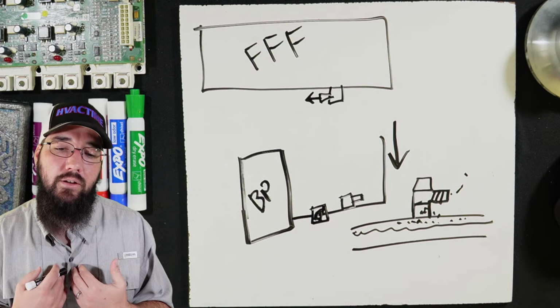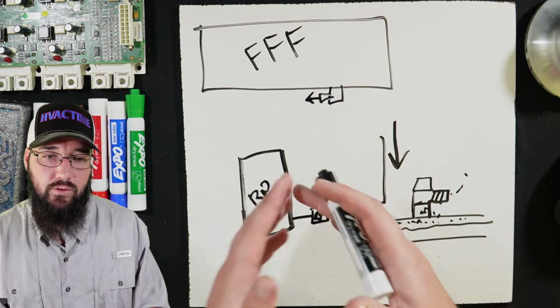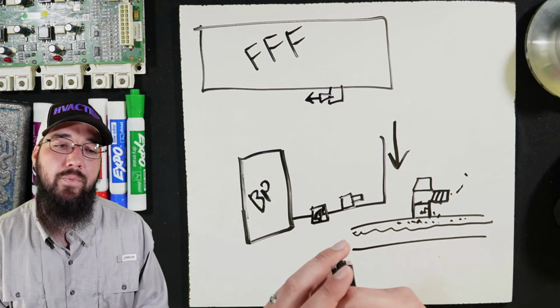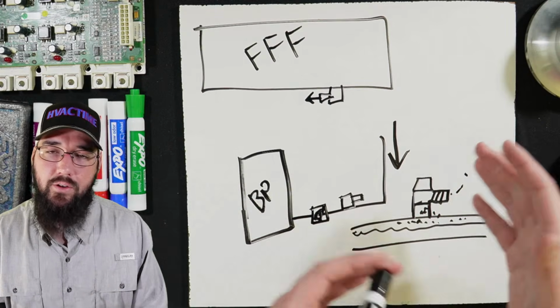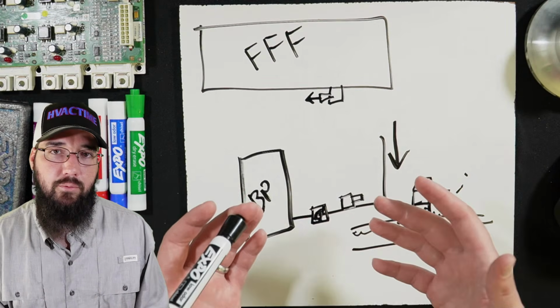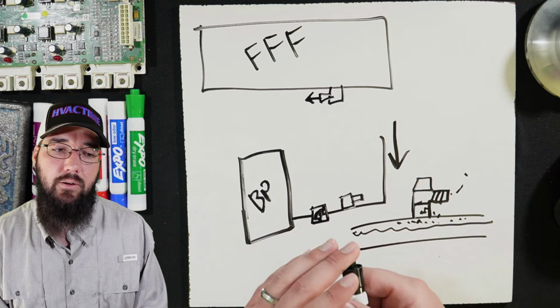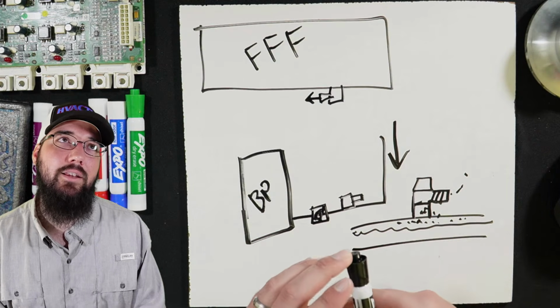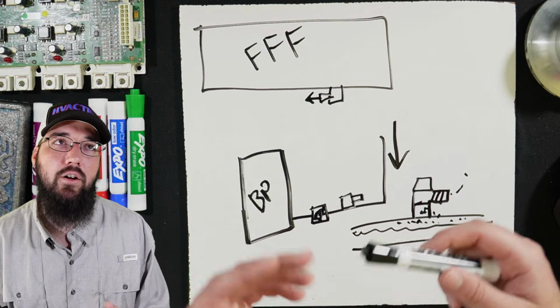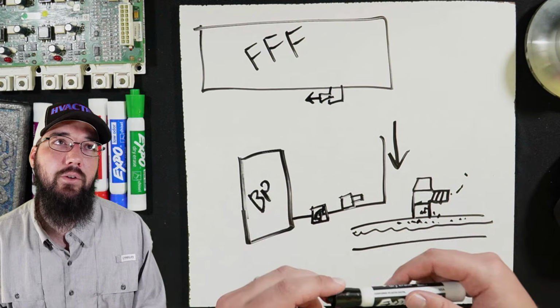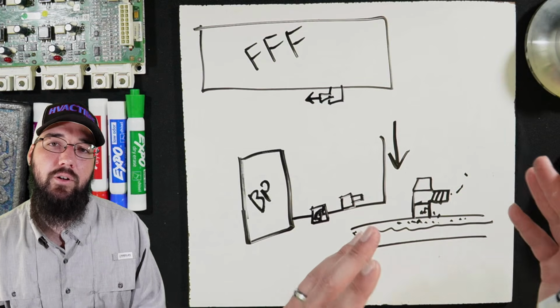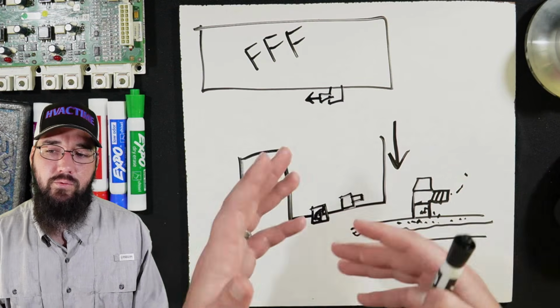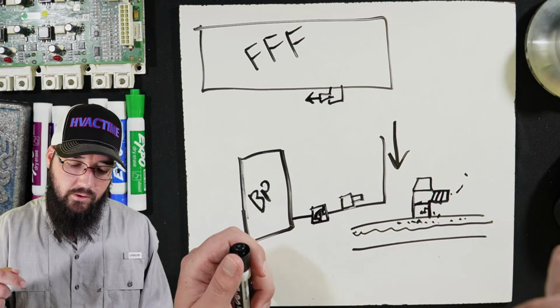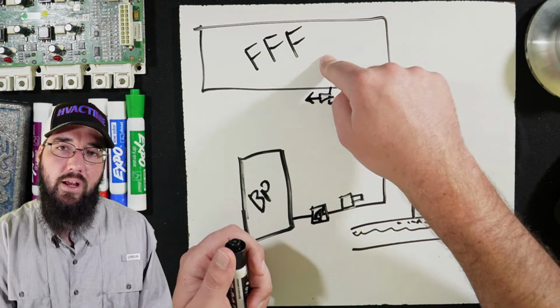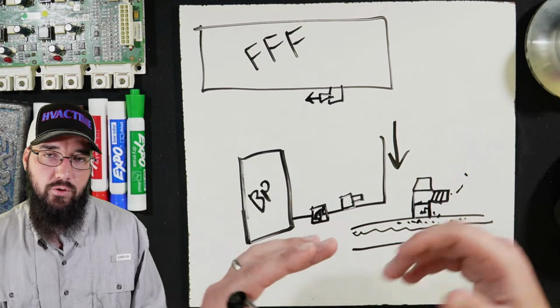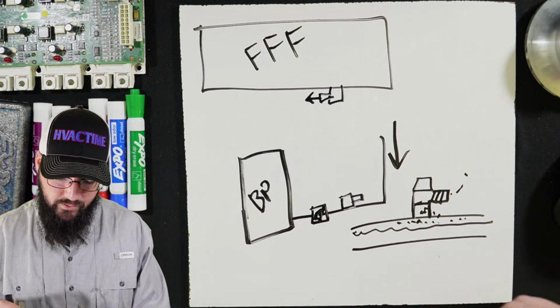But in my opinion, on these smaller machines, because these are small machines that we're discussing here, all these circuits are typically going to be less than 100 pounds of charge. Okay, I take that back. Some of these may scale into like 120, 150 pounds per circuit, but the majority of them are going to be less than 100 pounds for what we're describing here. And when we start getting into these other styles, that's when we start having higher refrigerant volumes.